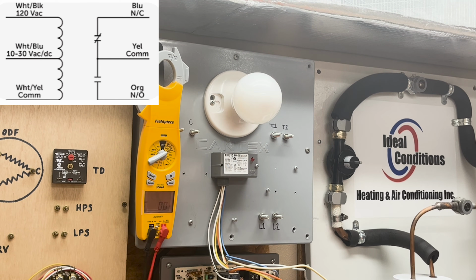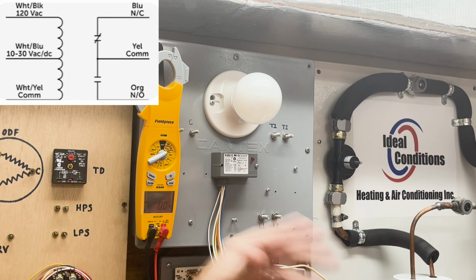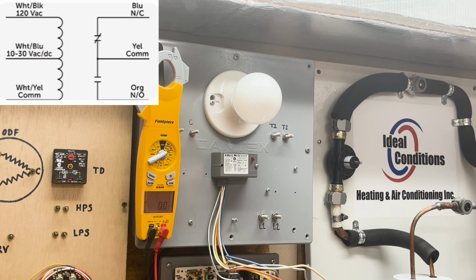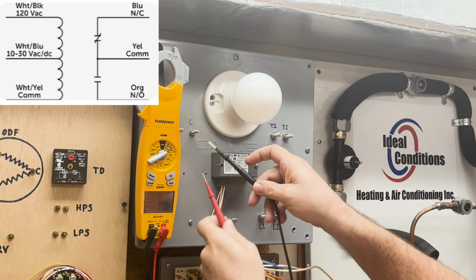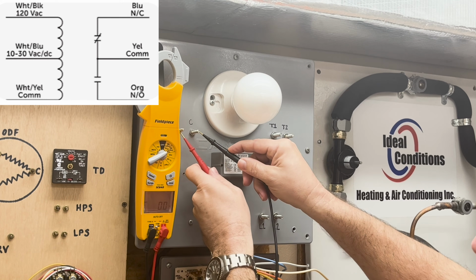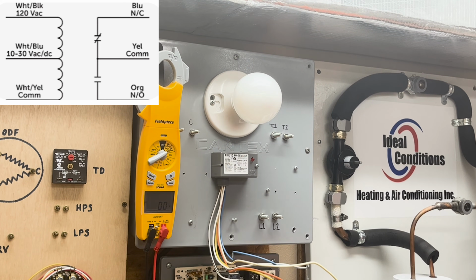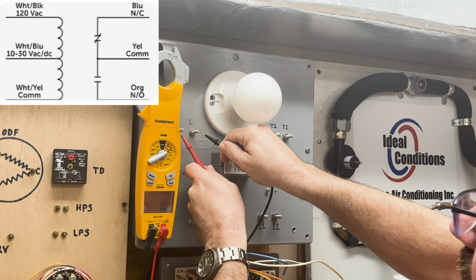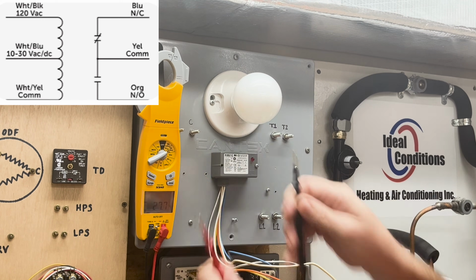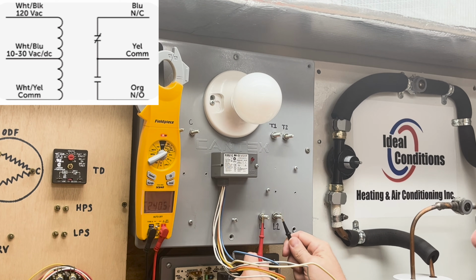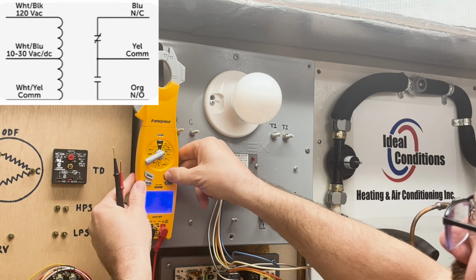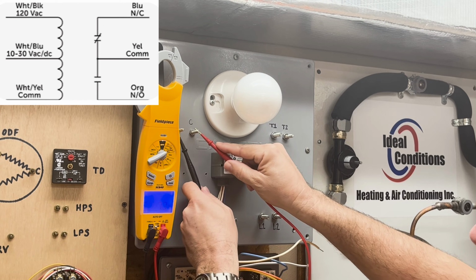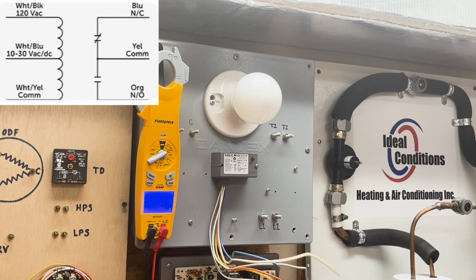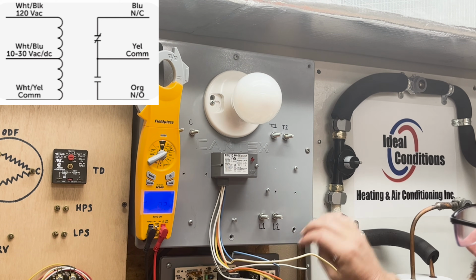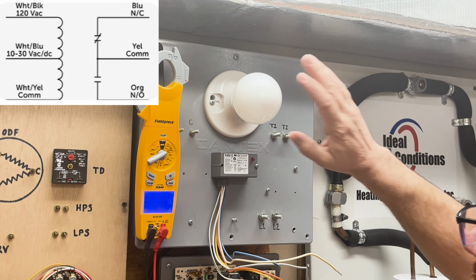I'm going to do this with the light on and with the light off, just so viewers have the opportunity to see it both ways. With the light off, let me turn the breaker on here. We have 27 volts. Then between L1 and L2, we have 240 volts. I'm going to try that again with the light on. We have 27 volts. And between L1 and L2, we have 240 volts. And our goal is to get this line voltage up here between T1 and T2 so our load can run.